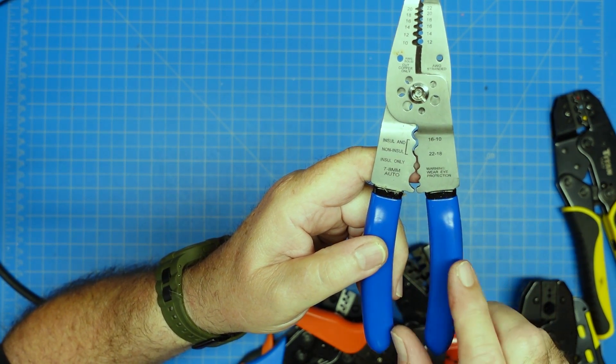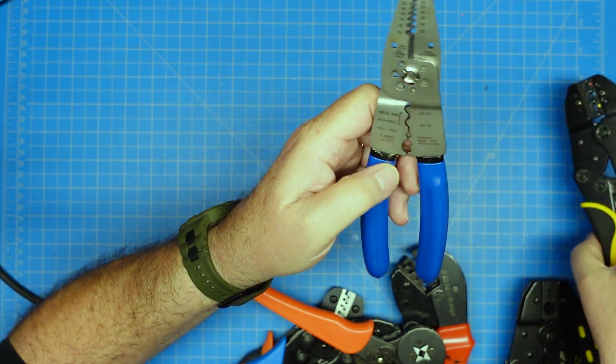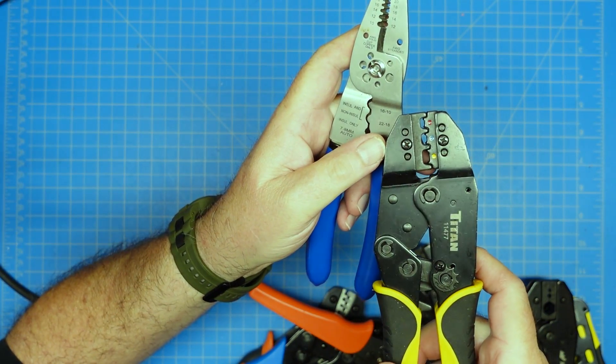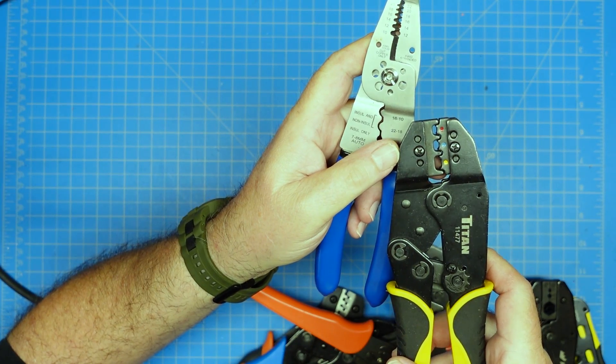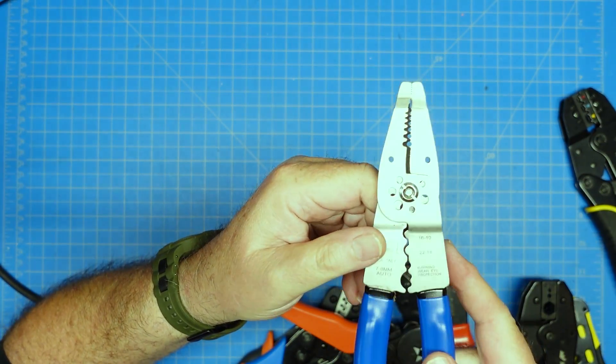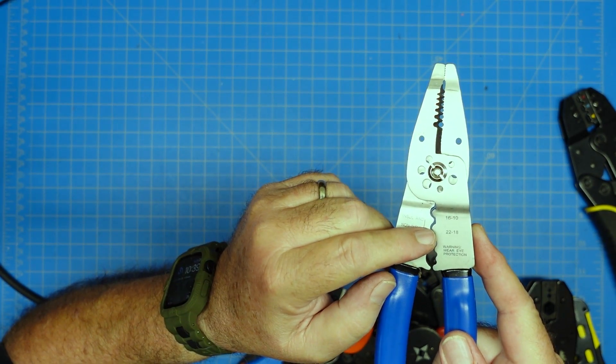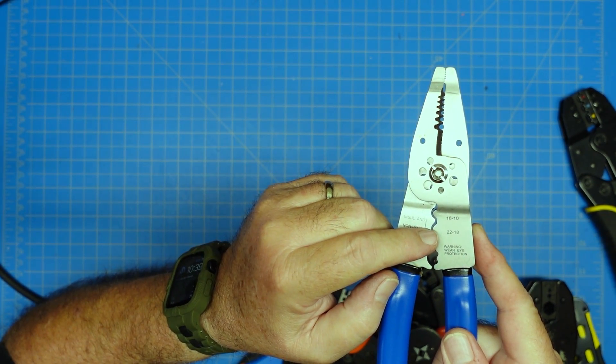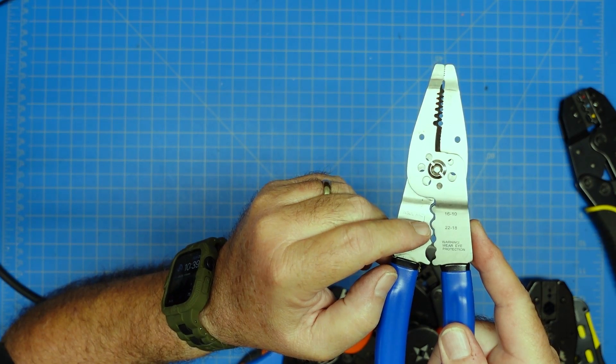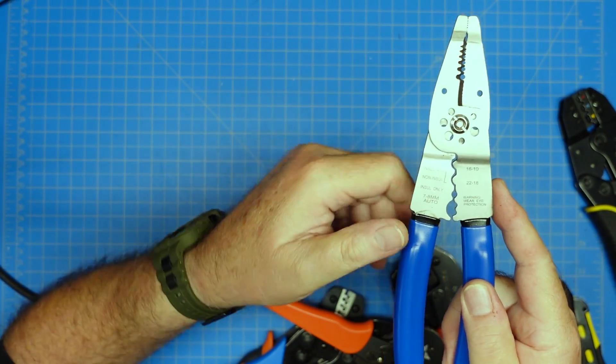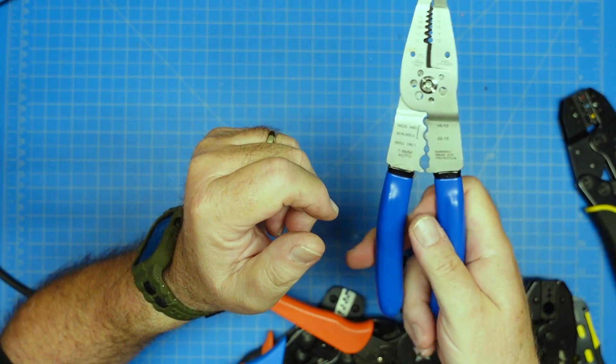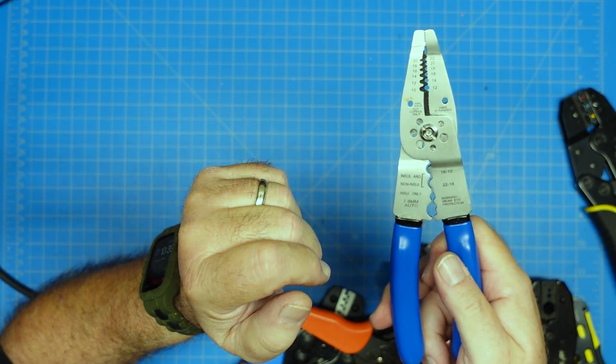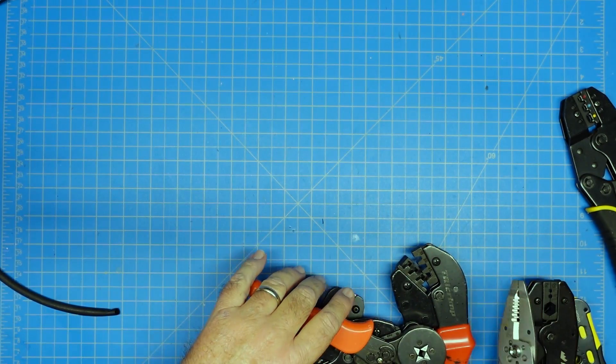And then down here on the bottom, you can see that we have two different kinds of things. So we have some specific auto-size crimps here. And then this is for insulated-only terminals. And these are for insulated and non-insulated. And we'll get to the difference in a minute. But basically on an insulated terminal, you have the plastic insulation around it. And you're squeezing the plastic insulation as well as the ferrule that's built inside the thing. And with a non-insulated one, you don't have the plastic. So there's this little dimple that you put the back side of the connector to. And the front side where it's split over in a U-shape goes here in the smooth curve. And when you squeeze this together, not ratcheting on this one, then it crimps it and makes a good physical connection.